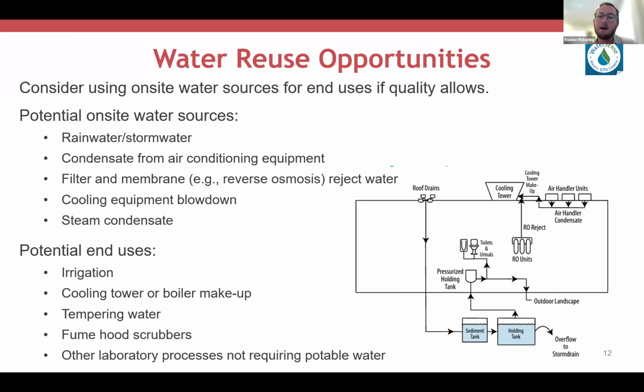Some sources of alternative water include rainwater, condensate from air handler and air conditioning equipment, and reverse osmosis reject water. The air handler condensate is a particularly good use for cooling tower makeup because labs have a lot of dehumidification requirements and pull in a lot of outside air. There's often a lot of condensate generated from these outside air units. This is generated in the highest amount in hot summer months when cooling tower demand is also really high. So there's a lot of good correlation between condensate recovery and cooling tower makeup demand.